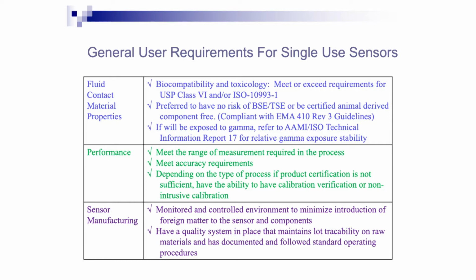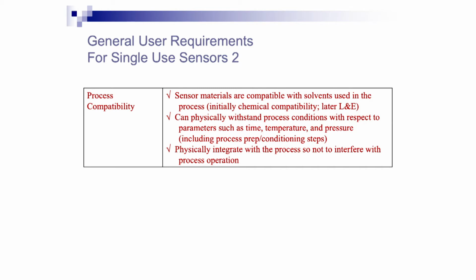And process compatibility, the sensors must be, again, compatible with all solvents used in the process, whether one with the product or one for conditioning. An initial step is to look at chemical compatibility. Later, as you move into the clinical trial phases, and of course commercial, leachables and extractables is pretty much required. And there's an organization called the BPOG that set out the testing standards that's been adopted by most of the end user companies in the industry for leachable extractables testing. But again, you have to look at all the parameters such as time, temperature, and then also you don't want to introduce a sensor that might restrict flow, damage cells, or create large back pressure.